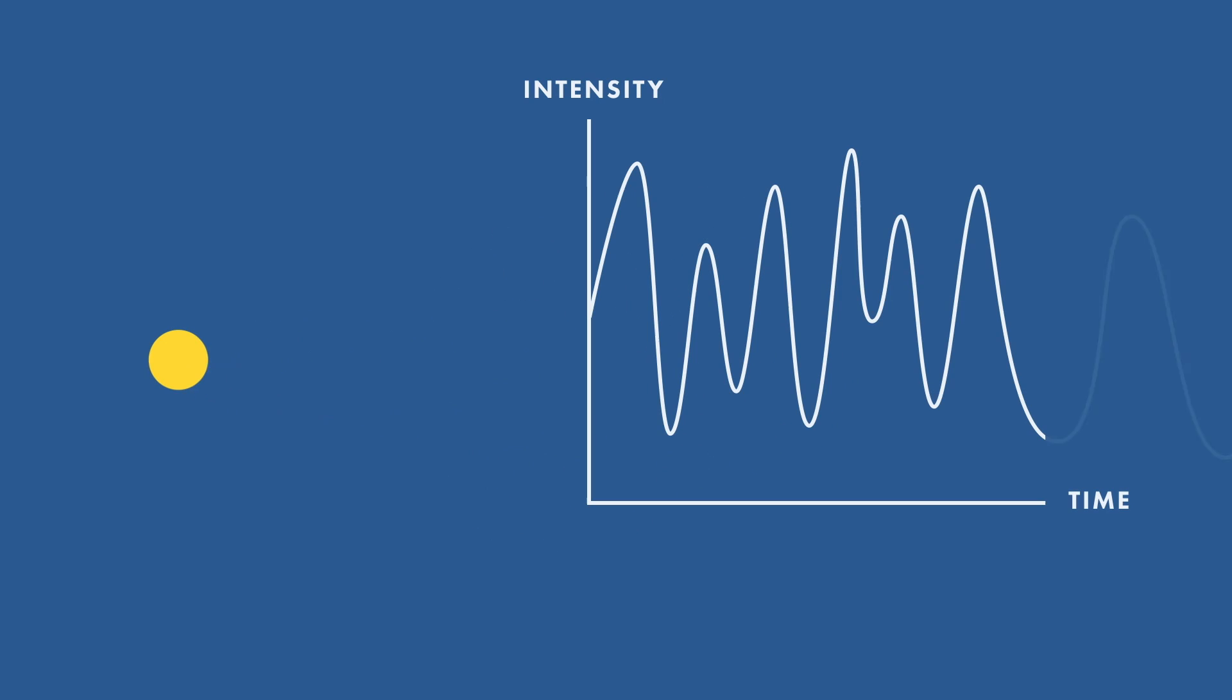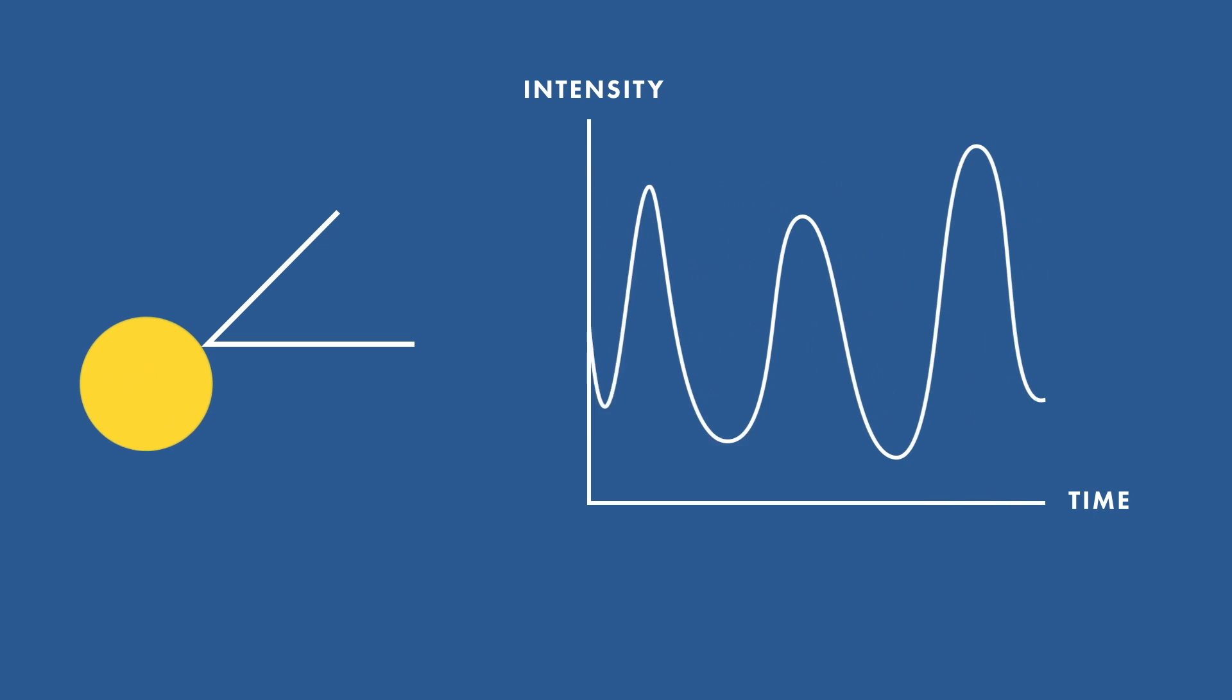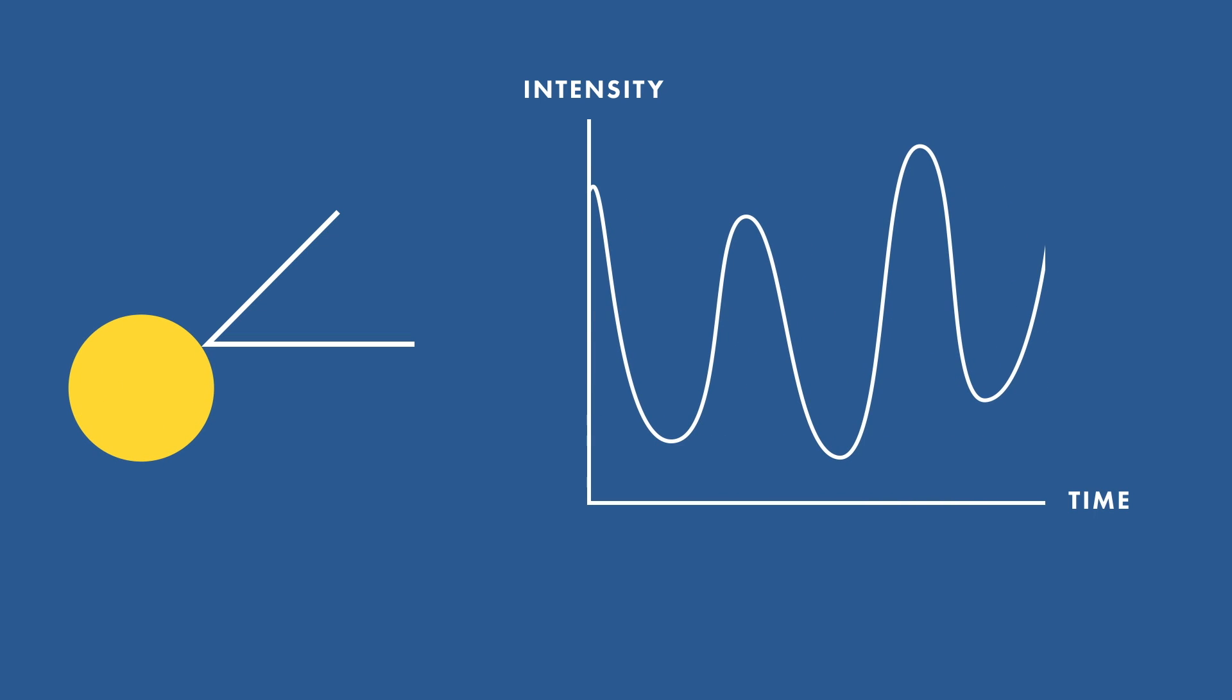A beam of light is shown on a dispersion of nanoparticles, which scatter light to a detector that is offset at a high angle. The Brownian motion of the particles creates a pattern of light at the detector that fluctuates at a rate that is a function of their size. The DLS is similar to the UV-Vis in that it requires a similar sample prep and is a cuvette-style instrument. It's a quick way to verify changes in surface chemistry and to monitor the stability of colloids.